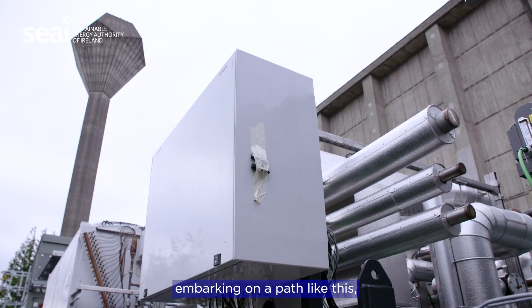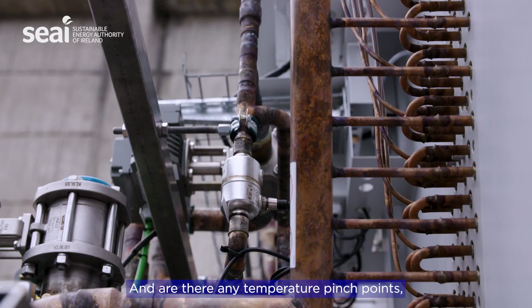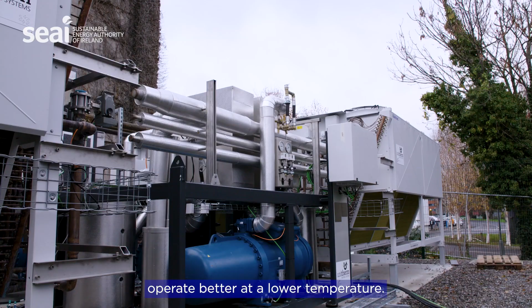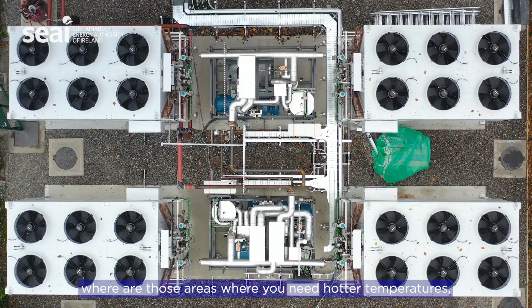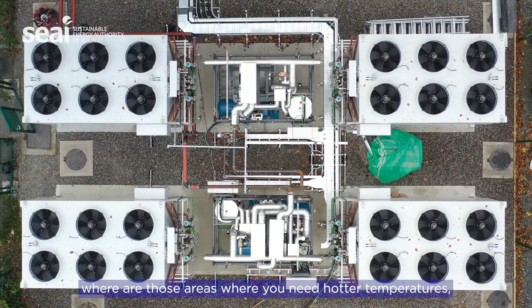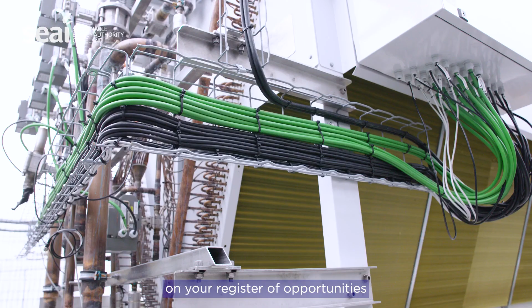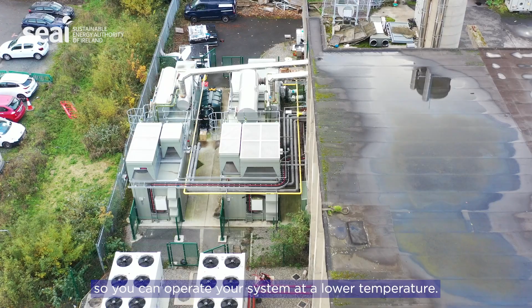In terms of advice for other universities embarking on a path like this: get an understanding of your system and whether there are any temperature pinch points. Heat pumps operate better at lower temperatures, so it's important to understand your heating network to see where you need hotter temperatures, for instance hot water. If it's possible to quantify those areas, you can identify them on your register of opportunities and find a way of re-engineering or designing these issues out so you can operate your system at a lower temperature.